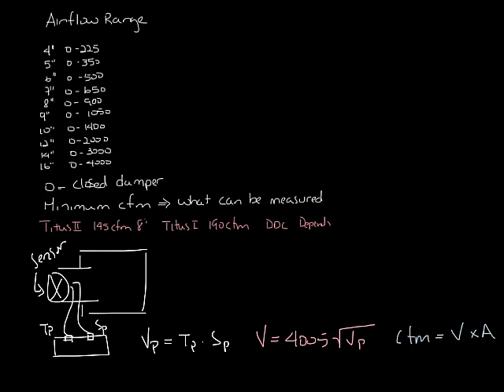So a good rule of thumb is that the pressure transducer in a controller needs about 0.03 inches of pressure differential. So using 0.03 as a guideline, you can calculate for each inlet size an approximate minimum CFM.